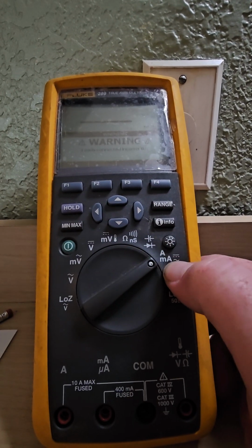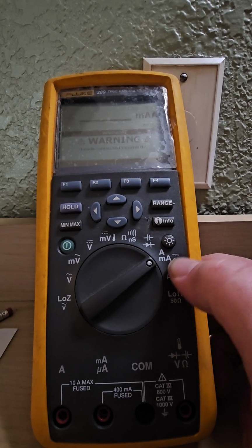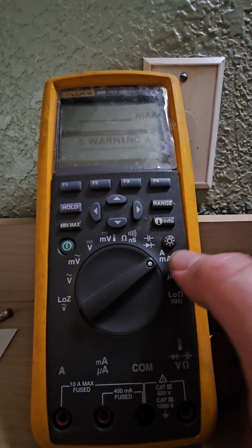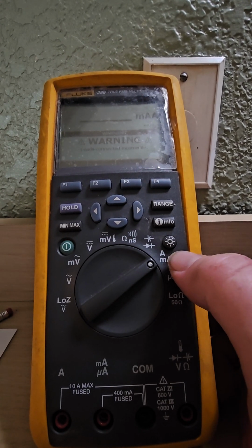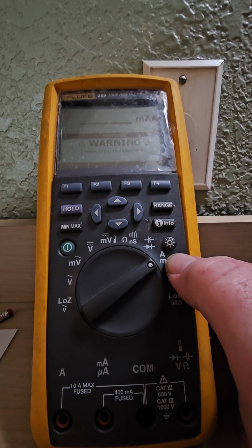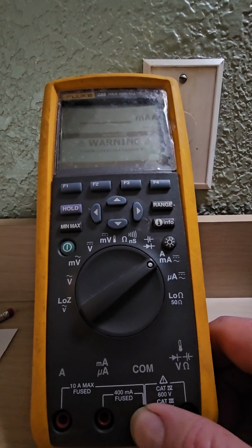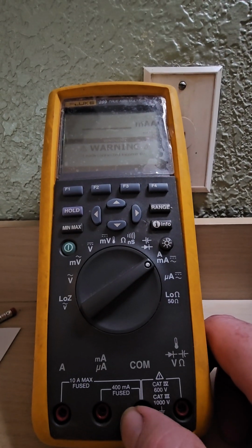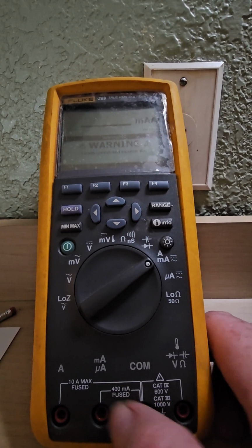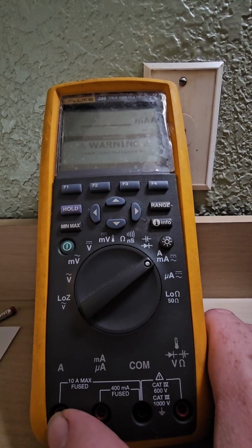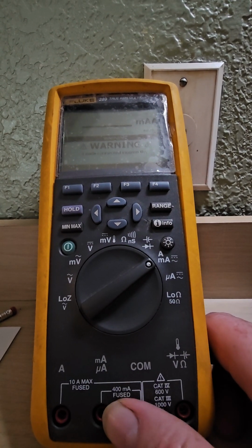This is your amps and milliamps. Now this one's important. You have to know the limitations of the meter that you're using, because you will blow this meter up in your hand if you overload the amp rating of your meter. I've seen it done. It'll fry a meter like you wouldn't believe. You also have to change your ports. It has to go through a fused port. You do not want to find out the hard way. Like this port has a 10 amp max. You run more than 10 amps through that, you will blow the fuse that's in there, and you can possibly blow this thing up.